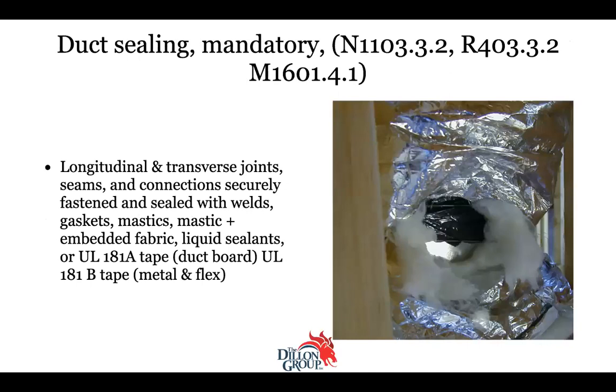Duct sealing has been mandatory forever. What kills me, and it just absolutely frosts me, is if you look at what the code says they're supposed to seal, it's the longitudinal and transverse joints, the seams and connections. That's what they're supposed to seal. What do we find? They seal the heck out of the insulation, not the longitudinal and transverse joints and the seams and the connections. I'll see a ton of mastic on the insulation. And when I see a ton of mastic on the insulation, I go, right, where's my pocket knife? And I'll open it up. And there's usually maybe a zip tie, or in this case, absolutely nothing.